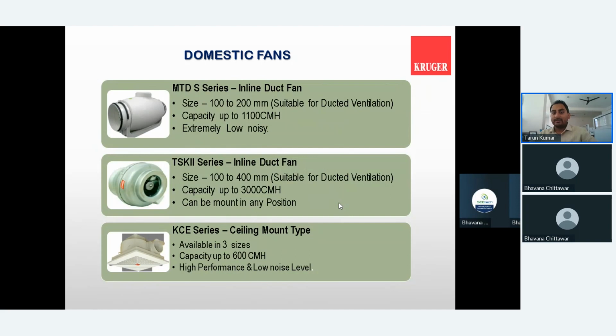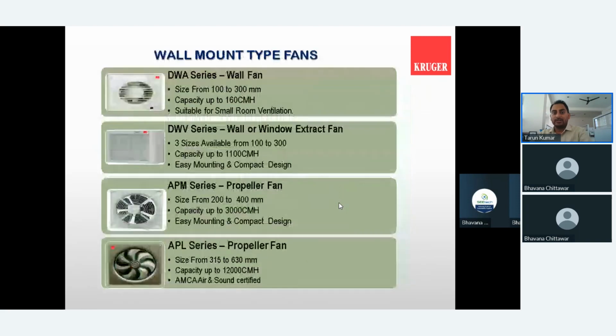So here it is basically known as a domestic fan, where capacity is less than 5000 CFM or 6000 CFM. Here again, your static pressure ranges from 10 mm static up to 50 mm static, where you can use a forward curve fan as well as a mixed flow fan, and our inline fan, which is available in both configurations, forward curve and mixed flow, as well as in the backward curve configuration.